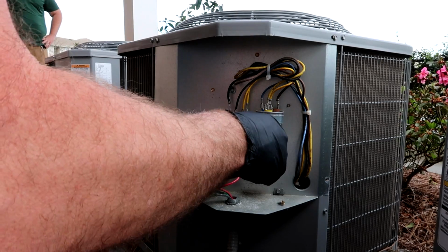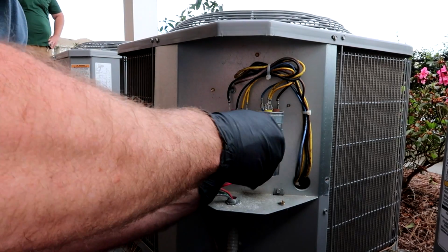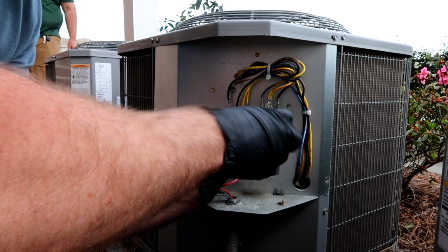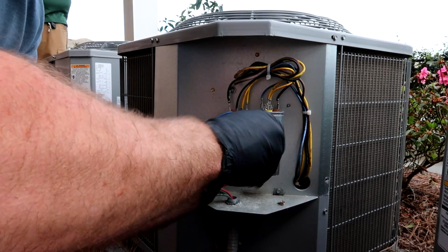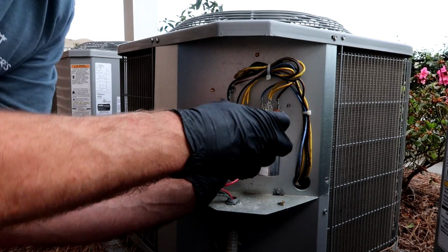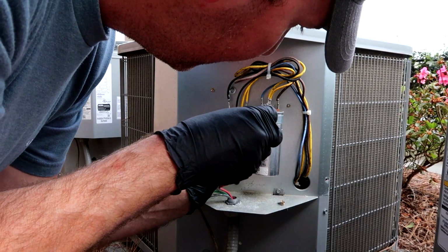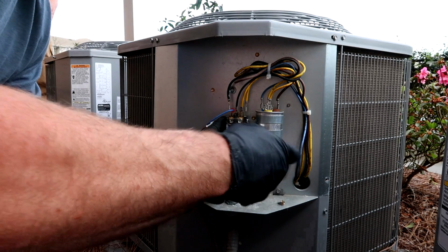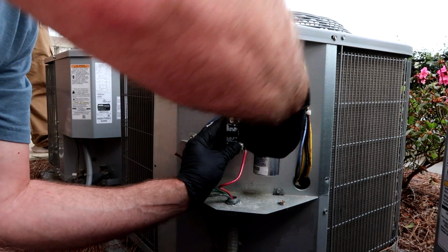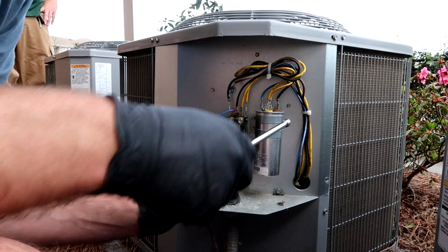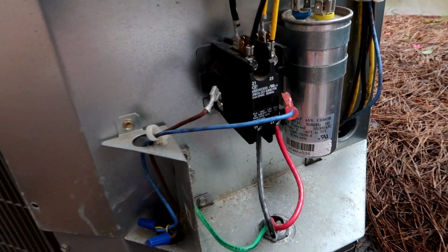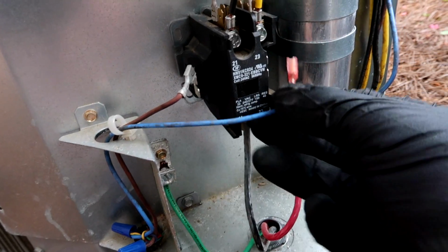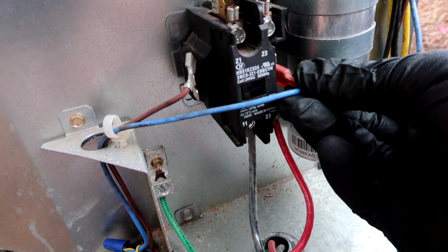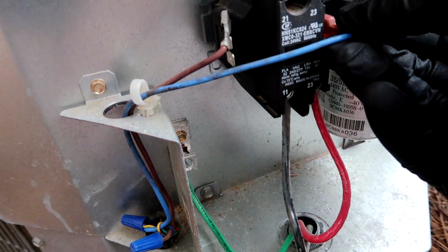Jay Booty, what's going on, Skid? We got a bad contactor, reading 1.5 ohms. Alright, new contactor is on. Hook the low voltage back up to the sides.